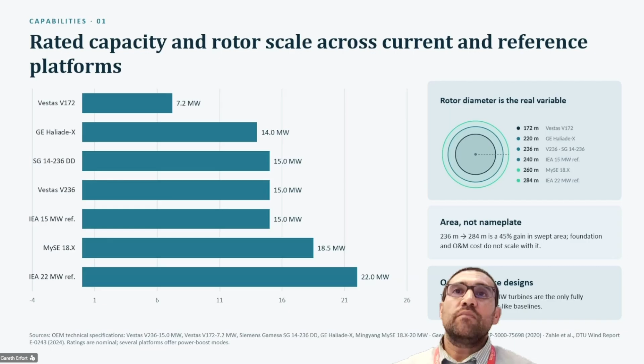When you talk about wind turbines, as Rian mentioned, they are intermittent. We know they will produce power when the wind blows, but I can't promise the wind is going to blow tomorrow at a certain wind speed. So when we talk about wind farms, we talk about something called the capacity factor - how many hours in an 8,760 hour year they've been producing power at full output. Capacity factors in good locations can be 30 to 40% onshore. I think, and I stand to be corrected, turbines in South Africa across the REIPP programs are tipping out just under 30% average capacity factor. In the future, we're looking at wind farms that can reach capacity factors between 50 and 60%.